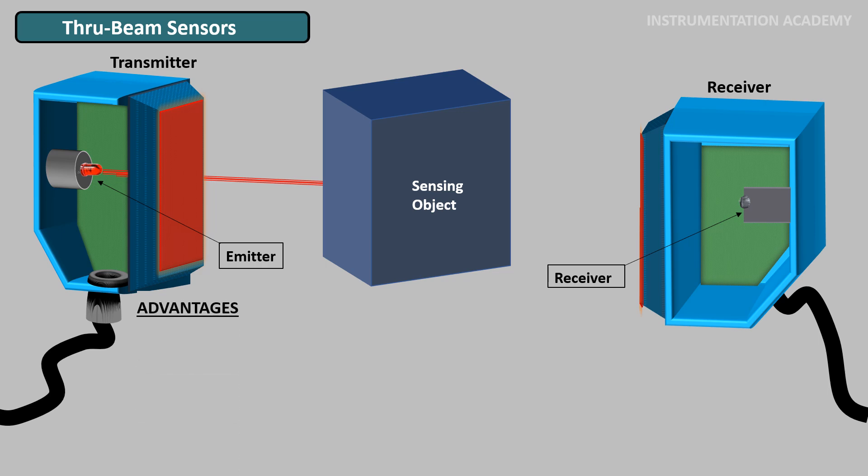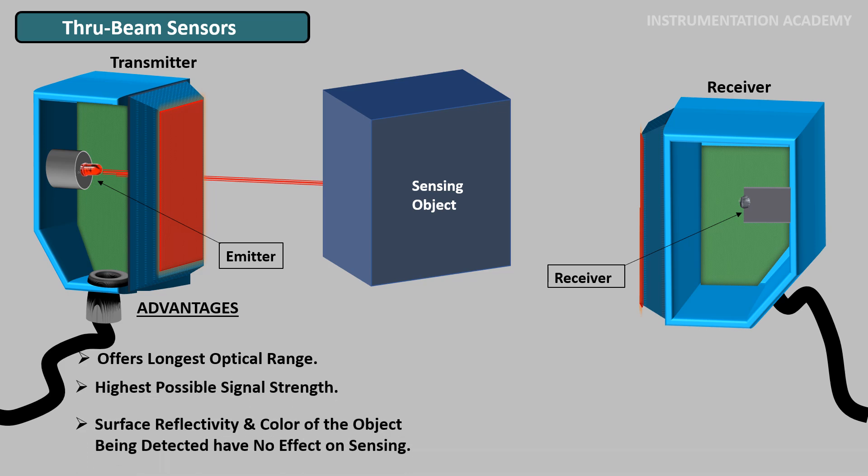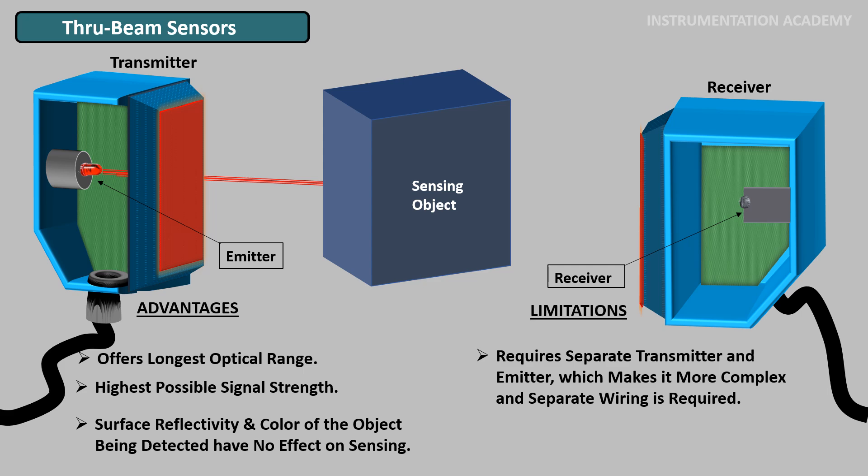Advantages of through beam sensors: As the light from the transmitter falls directly on the receiver, through beam sensors offer the longest optical range and highest possible signal strength. Surface reflectivity and color of the object being detected have no effect on sensing. Limitations: This type of setup requires separate emitter and a separate detector which makes it a bit more complex to install and wire. Alignment of emitter and receiver can be difficult.